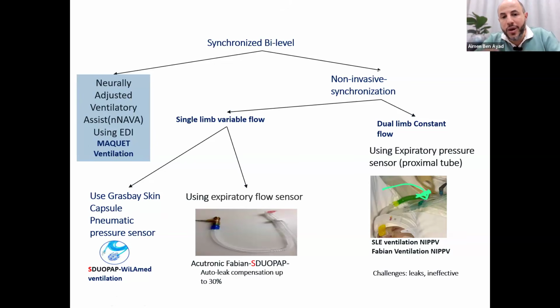The companies try to find alternative ways to make it synchronized but less invasive. We used to have the capsule, the abdominal capsule over the baby's liver, sensing the baby's abdominal movement. The more the abdomen moved, the ventilator gave the breath, provided through the single limb variable flow. The issue is that most companies no longer provide the capsule. When the baby has shallow breathing, you cannot sense it, or if the baby is breathing very, very fast, it's hard to catch the baby's breath. So it has a lot of artifacts, and it's not truly synchronized unless the baby is breathing comfortably.